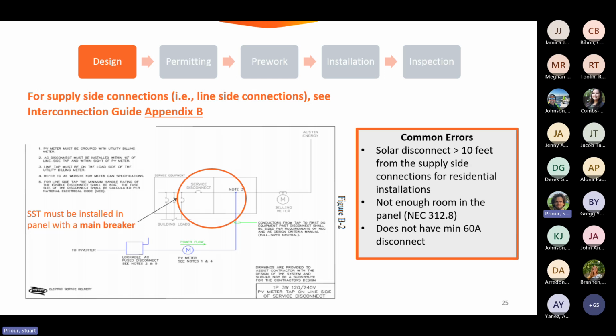Another common error is that there is not enough room in the panel. So if you refer to 312.8 in the NEC, that'll give you some guidelines as far as tapping in a location that has an appropriate amount of room. And also you've tapped and you haven't installed a 60 amp main disconnect, or at least the enclosure is not rated for 60 amps. So like I was saying, even if you've got a system that's 20 or 30 amps and you can get away with a 30 amp disconnect, the enclosure itself still needs to be rated for 60 amps if it's a supply side connection.